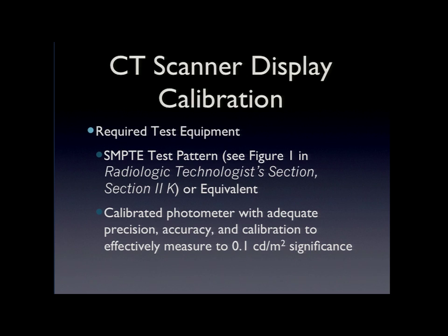machines. But most of them, what happens if there's a software upgrade or a data dump, the imaging patterns get dumped, but you can retrieve them from the service mode. And so a lot of service engineers have given us access to that, so we can bring them back out and evaluate using the SMPTE patterns.